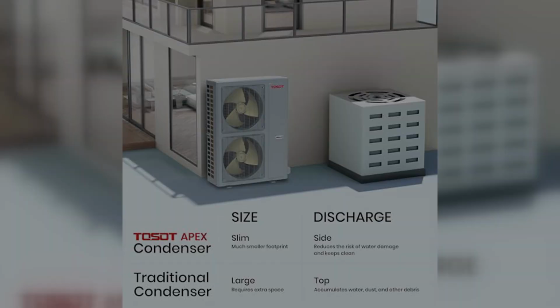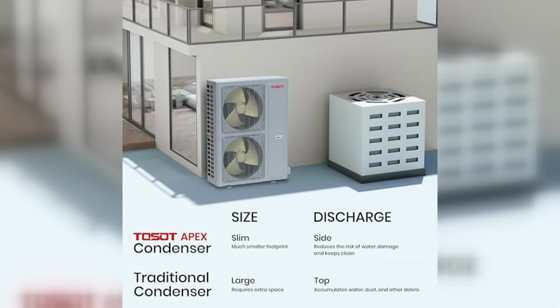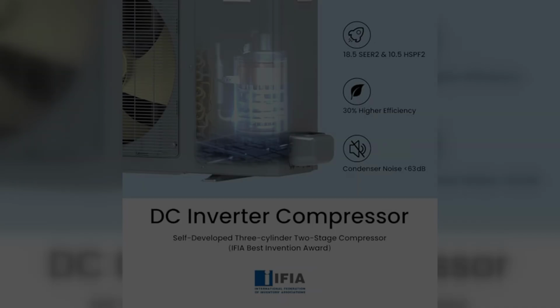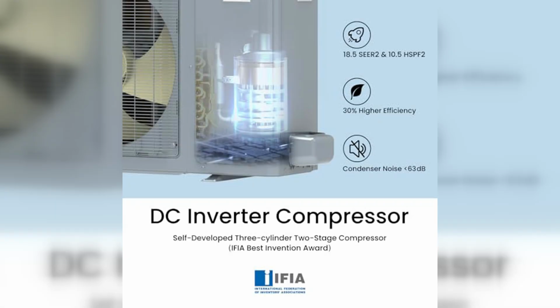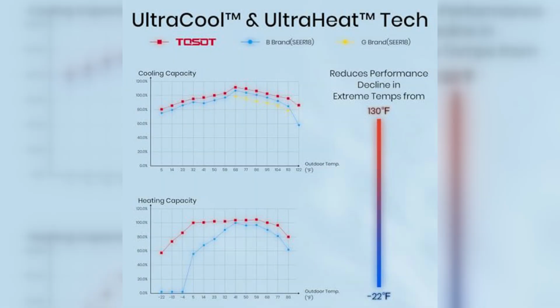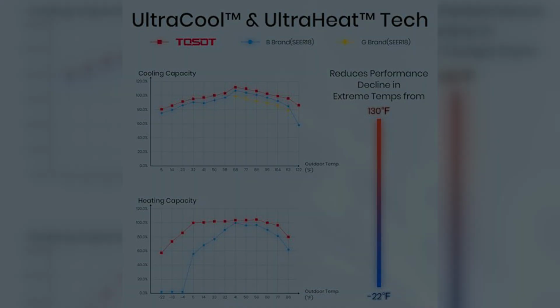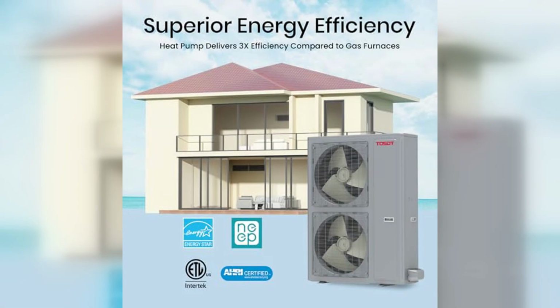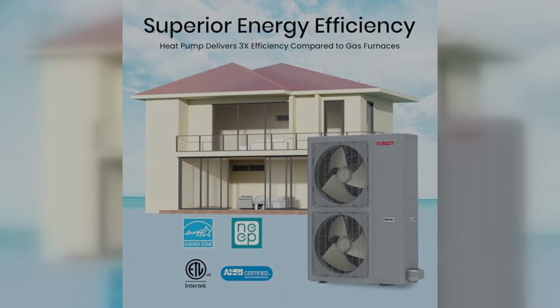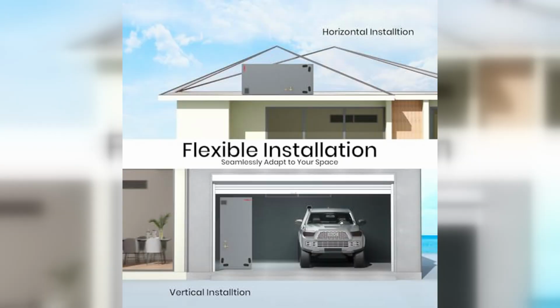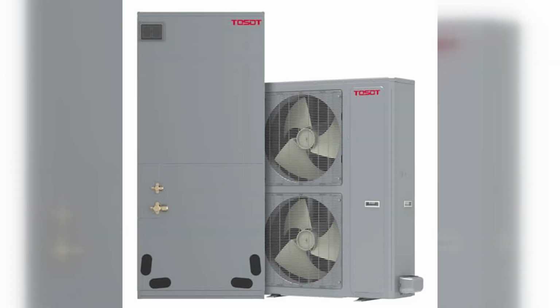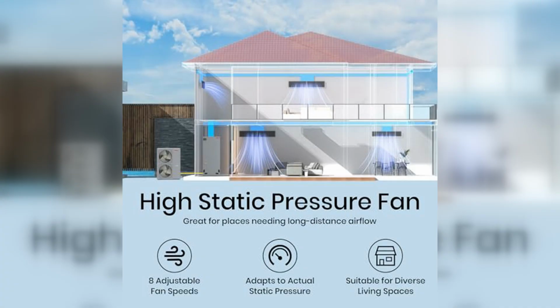That said, there are some realistic trade-offs to keep in mind. While TOSOT is a subsidiary of a major global manufacturer with a solid reputation for engineering, you are entering the world of modern inverter-driven electronics. These systems are more sophisticated than the dumb AC units of the past, and that complexity means that if a control board or an inverter component fails, you aren't just calling a local handyman to swap out a capacitor. You're going to need a technician who is trained on variable speed inverter systems. You should also verify that your local HVAC contractors are familiar with the brand, as parts availability and service support can vary by region compared to the long-established legacy brands that have dealer networks on every corner.